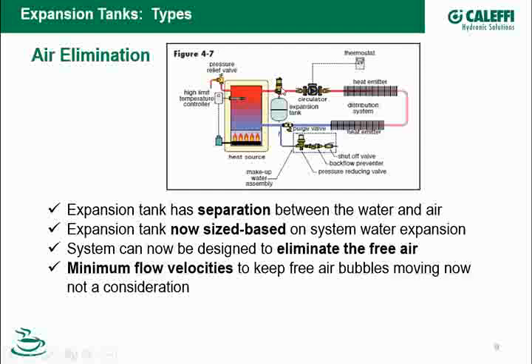In the diagram, I have my air separator with an air vent on the top, and I have high point air vents from the system. I get rid of the air, and the problems go away. Additionally, with air elimination, since I'm not as concerned with entraining the air bubbles constantly in the system to bring them back to the air control device on top of the boiler, I now have much more freedom in my flow velocity throughout the system.